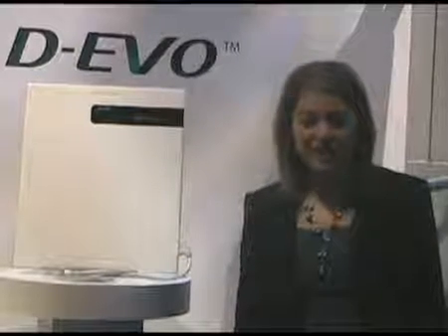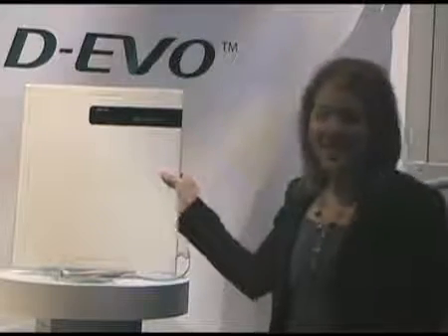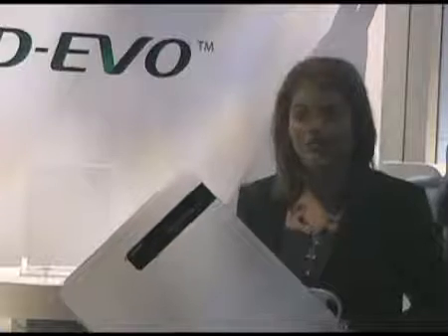Why it's so smart is it's a new flat panel detector in a cassette-based form that is an easy retrofit to existing radiographic rooms. It's the same size as your existing cassettes for film screen and CR, and it's also very lightweight. In fact, it's the lightest weight 14x17 DR cassette on the market today at only about six and a half pounds. You can see it's very thin, and that makes it an easy retrofit into any type of existing radiographic equipment.